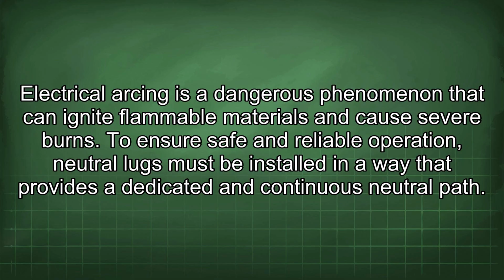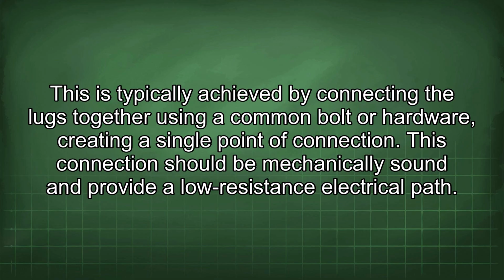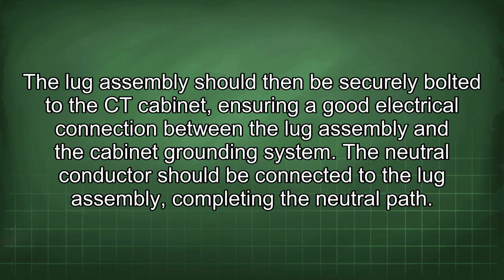To ensure safe and reliable operation, neutral lugs must be installed in a way that provides a dedicated and continuous neutral path. This is typically achieved by connecting the lugs together using a common bolt or hardware, creating a single point of connection. This connection should be mechanically sound and provide a low-resistance electrical path. The lug assembly should then be securely bolted to the CT cabinet, ensuring a good electrical connection between the lug assembly and the cabinet grounding system. The neutral conductor should be connected to the lug assembly, completing the neutral path.